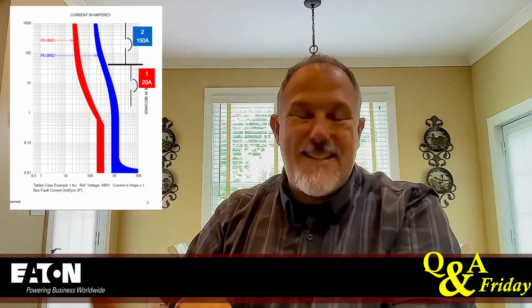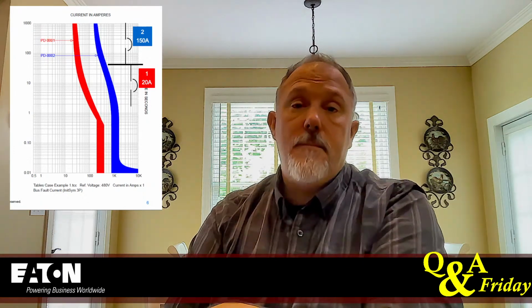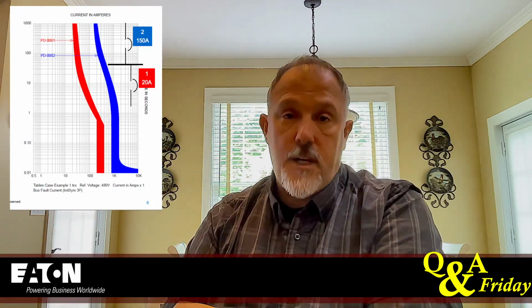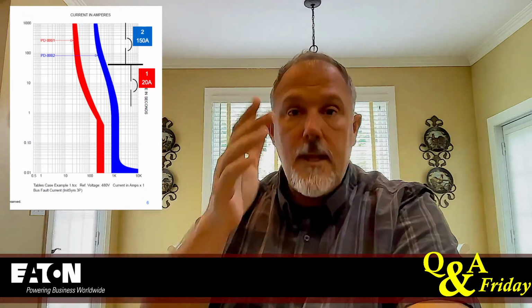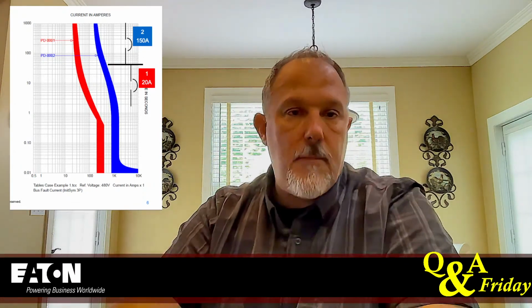The challenge, Willie, is if you can't lower that low enough. So in the case of this one here, I've got say a 150 amp panel downstream, or say a 200 amp panel downstream. If I increase the upstream overcurrent device size large enough and I can't dial it down, then I'm changing out a panel if I've already installed it. But to your point, if I dial it down and I lock the cover, now I'm into, I think it's 240.4(D). Man, I don't know. I think it's 240.44. Man, I don't know.